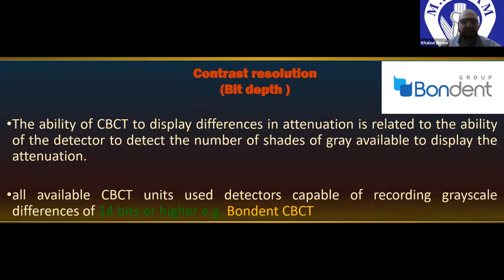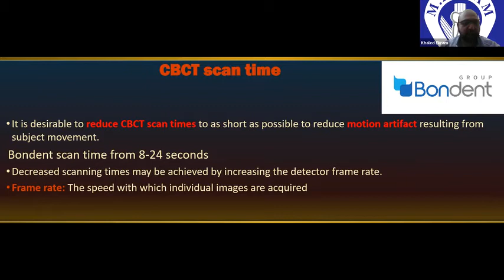CBCT scan time. This is also a very important factor, that when the scan time increases, this means that we have two problems. First problem is the higher exposure dose to the patient. Second is the possibility of the patient to move within the long scan time, which can produce haziness or motion artifacts. So the scan time here, for example, if we take a Bondent as an example, we have from 8 to 24 seconds scan time according to the irradiated area. If the irradiated area is small, we will go to the 8 seconds. And if we have a large field, we will go to the 24 seconds.